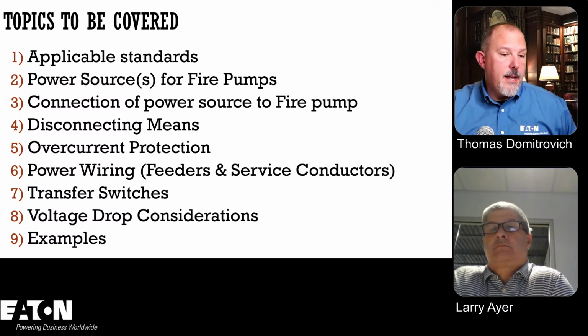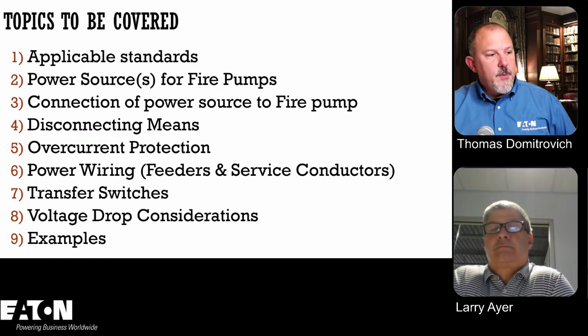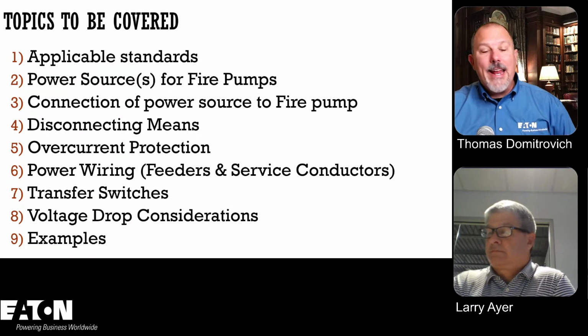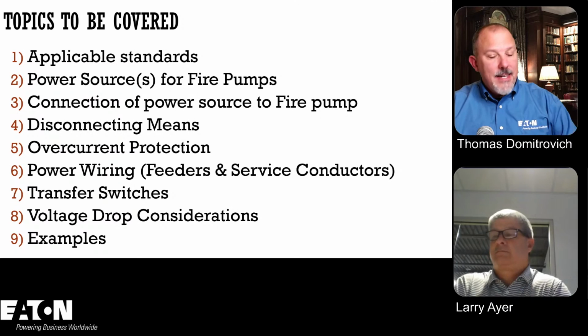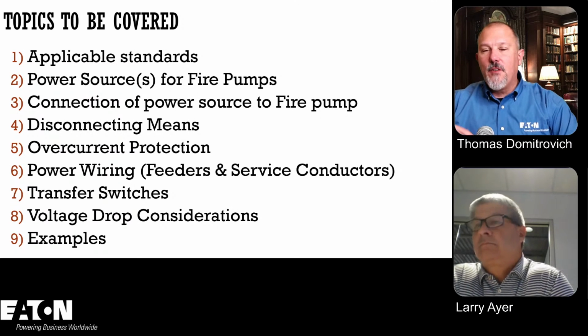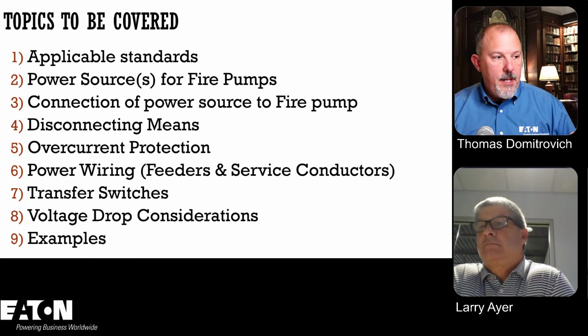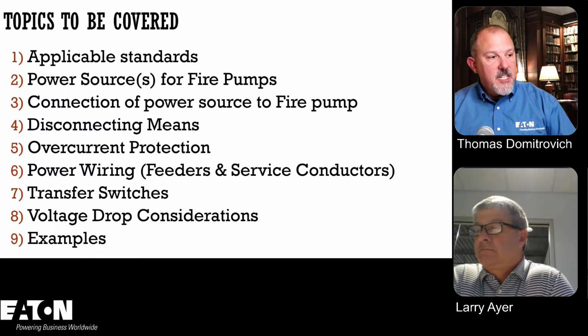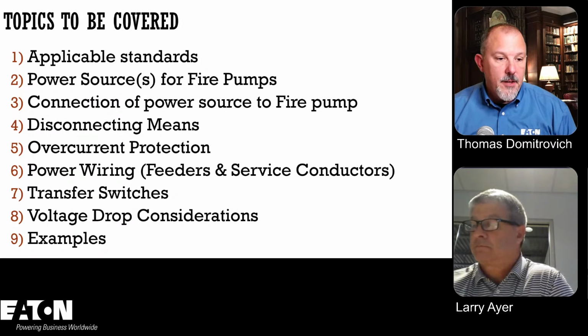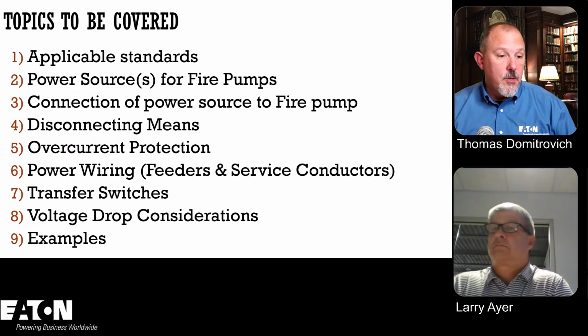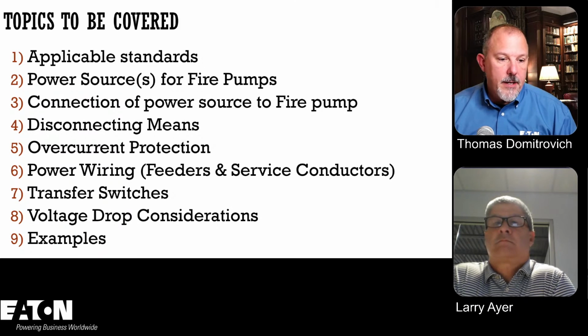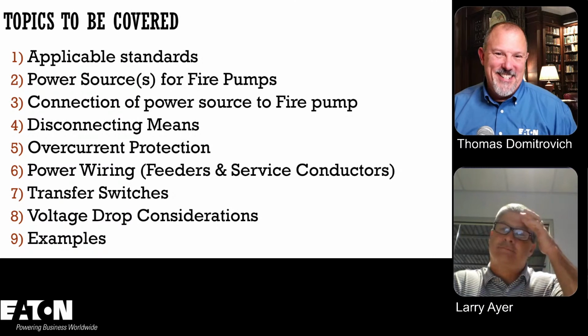So Brian Rock is saying that the type 2 enclosure, and I've got to look at this, provides a degree of protection with respect to harmful effects on the equipment due to ingress of water, dripping, and light splashing. So a type 2 enclosure is not meant for outdoors like a type 3, but there is dripping and light splashing. So that might be another reason why you have a type 2 minimum. So good feedback, Brian. I appreciate that feedback. Yep. And Bruce says it better not be a wet location.